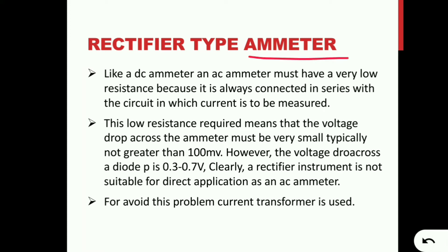An ammeter must have a very low resistance so we are able to measure the current. Both DC ammeter and AC ammeter must have very low resistance because they are always connected in series with the circuit in which current is to be measured. The voltage drop across the ammeter must be very small, typically not greater than 100 millivolts. However, the voltage across a diode is 0.3 volts to 0.7 volts, so clearly a rectifier instrument is not directly suitable as an AC ammeter.